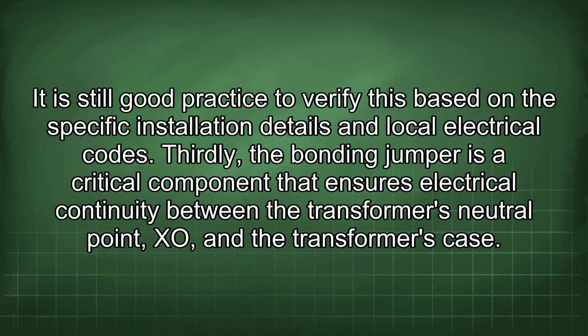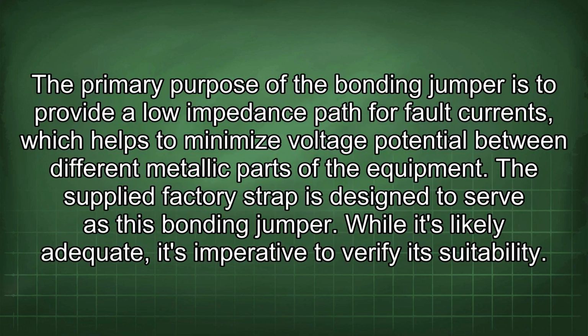Thirdly, the bonding jumper is a critical component that ensures electrical continuity between the transformer's neutral point and the transformer's case. The primary purpose of the bonding jumper is to provide a low impedance path for fault currents, which helps to minimize voltage potential between different metallic parts of the equipment. This supplied factory strap is designed to serve as this bonding jumper. While it's likely adequate, it's imperative to verify its suitability.